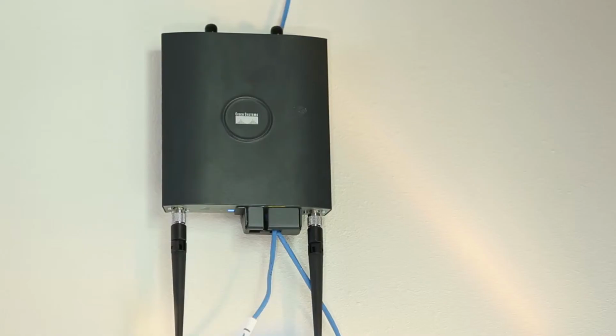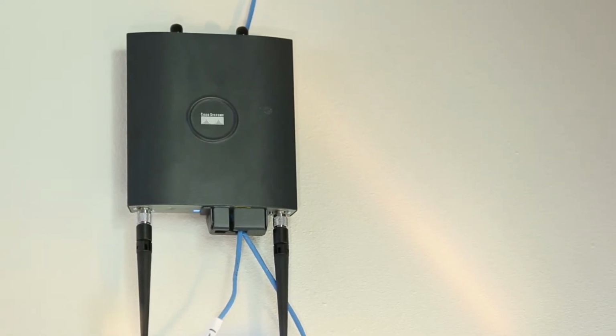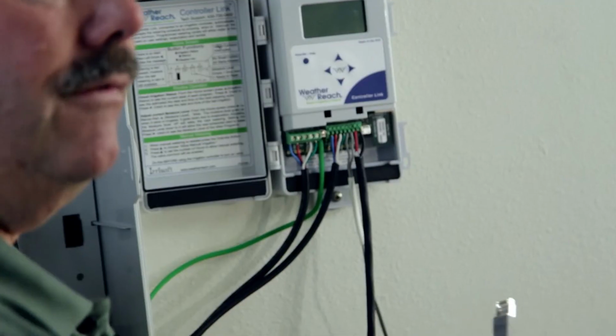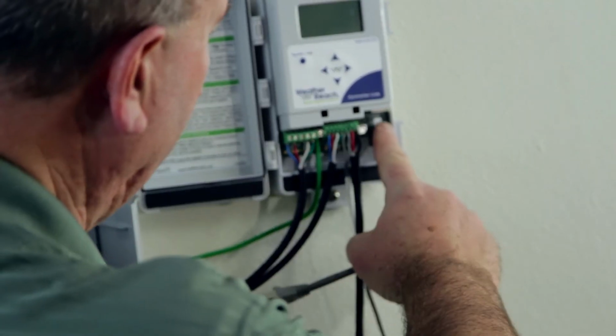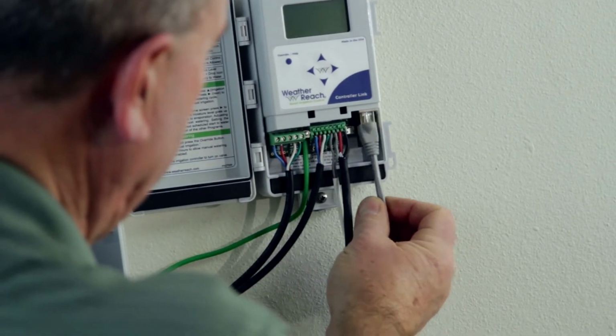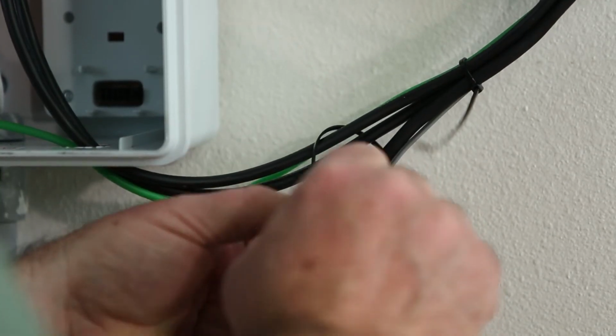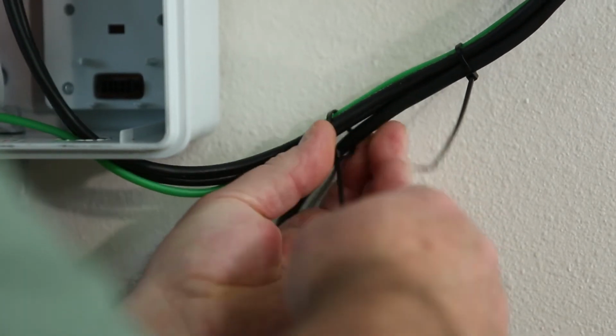Controller Link needs to be connected to the internet. If you are using Wi-Fi, the setup steps are in the next video. Make sure the Wi-Fi access point is within range of the controller link. You will need the access point ID and passphrase. If you are using wired Ethernet, connect a Cat5 cable from the router to the RJ45 Ethernet socket in the controller link. Take a minute to clean up the cable runs and secure them with wire ties.